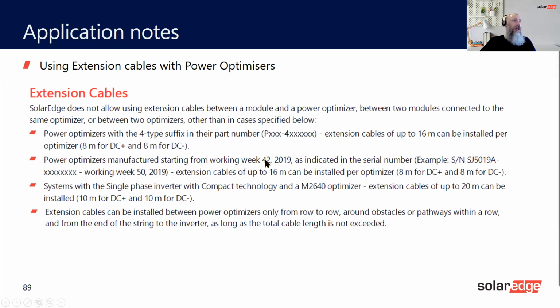And you can see on here the week 4219, and that's represented here. So the S and J is the manufacturing plant. The 50 is the week number, and the 19 is the year. And that's the same for all SolarEdge products. The first two letters are the manufacturing plant where it came from. The next one is week and then year. So anything that has a 4 on it or has this information, you can extend up to 8 meters plus or minus.